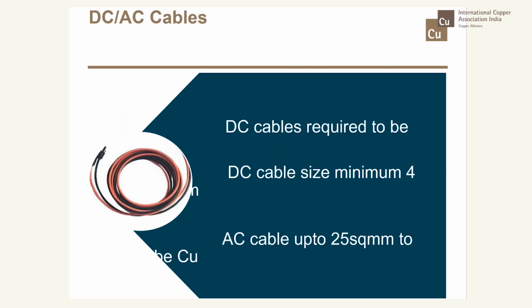Moving on, next are the upcoming recommendations of DC and AC cables by the National Electric Code. DC cables to be 4 square mm, and the DC cable has to be copper conductor. And AC cable, fortunately, from the inverter to the AC distribution board or the point of common coupling needs to be copper up to a capacity of 25 square mm.